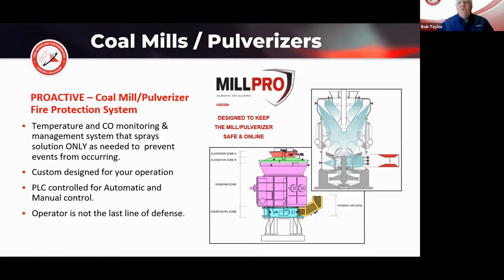Coal mills and coal pulverizers over the years have been known to have explosions. Some people call them puffs, some call them other things, they're a transient pressure excursion - it's an explosion, whatever you want to call it, and it's not a good thing. They do happen, and when you think about it, during a milling or pulverizing function you're reducing the size of particles. Often you've got airflow in there, it's being put into airborne conditions, and it just takes heat and whatever, and you now have all the conditions for an explosion to take place.